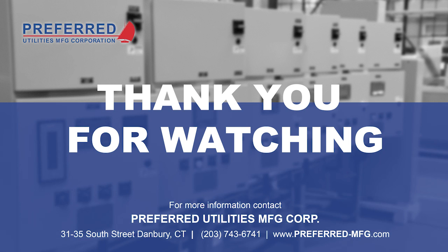Do you usually provide fuel supply and return in one containment pipe if required, or do you run your supply and return in separate containment pipes for each line? In most jurisdictions, you can do it either way, and it's less expensive to run both your supply and your return in one containment pipe. In fact, I think there's prefab piping that has an outer steel wall, and inside is hydraulic hose that has your supply and your return. Our New York City representative sells Brugg containment piping, and I think that's an option with them. But code allows you to do it either way, but it's less expensive to put your supply and return in one containment pipe.